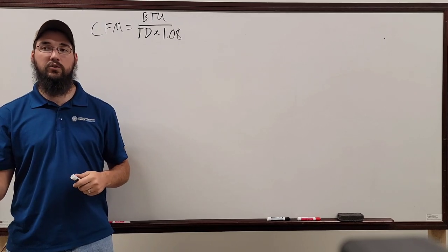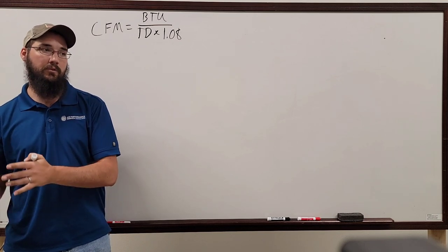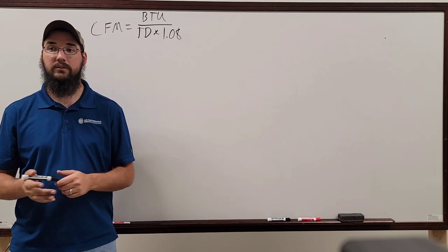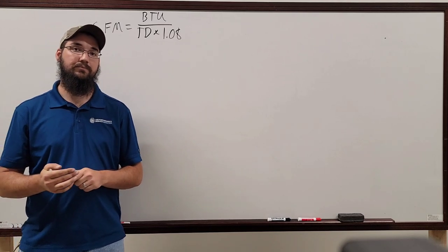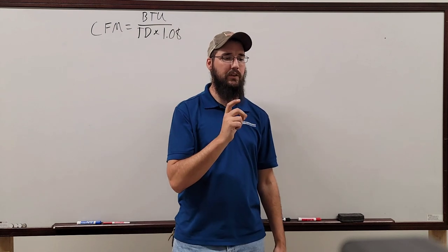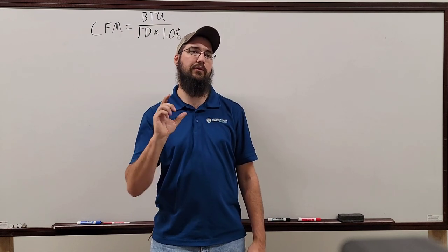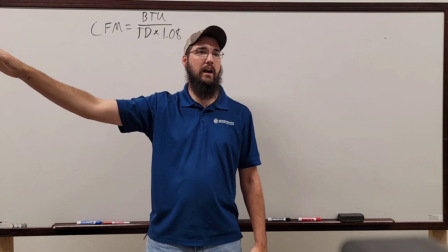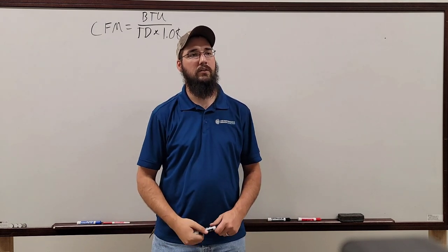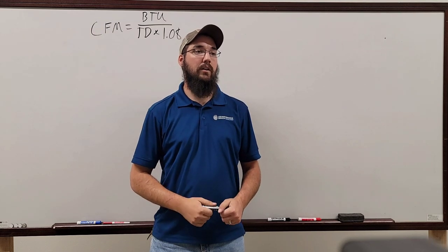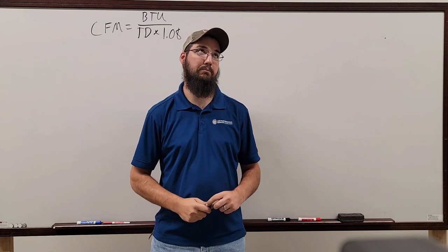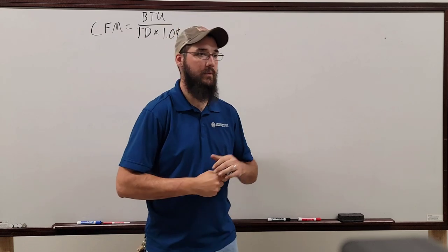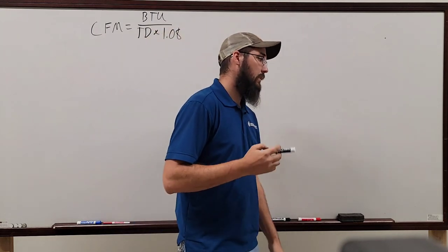Trying to check in the cooling season what your CFM are through the heater, and it kicks on into a lower fan speed because of it. Follow me? Do we have to switch our speed taps on the unit? Yeah, usually there's a separate relay. One relay will engage off a W signal, say low speed fan for heat, and then G would just activate a high speed fan for cooling. So you end up having to basically program the equipment that way. Yeah, it becomes a pain. I didn't know that.